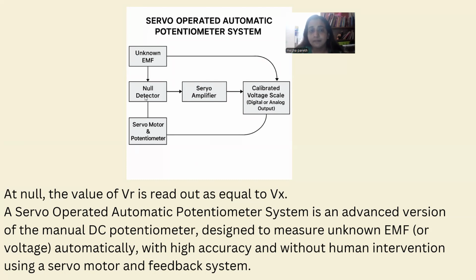We apply an unknown EMF here, and we can get the unknown EMF by using the servo-operated potentiometer system. At the null, the reference voltage is read out as equal to the voltage to be measured. A servo-operated automatic potentiometer system is an advanced version of the manual DC potentiometer, designed to measure unknown EMF or voltage automatically, with high accuracy and without human intervention, using a servo motor and feedback system. So human error is reduced. Human error and systematic error are also reduced in the system.